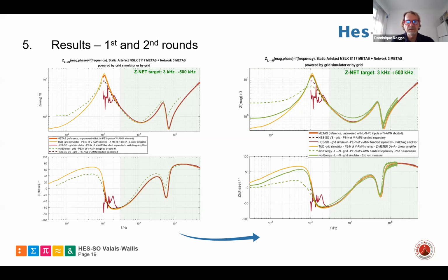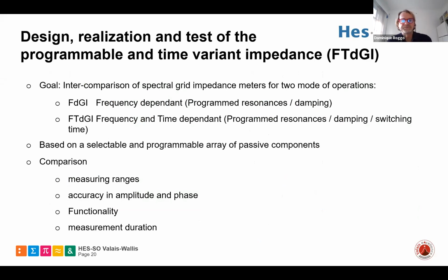We can see that there is a very good correspondence despite the differences in techniques and analysis used. It also gave the chance to fine-tune equipment within the process. So we are very satisfied with these results, at least in the PLC frequency range. There is very, very good correlation between devices in the energized tests.